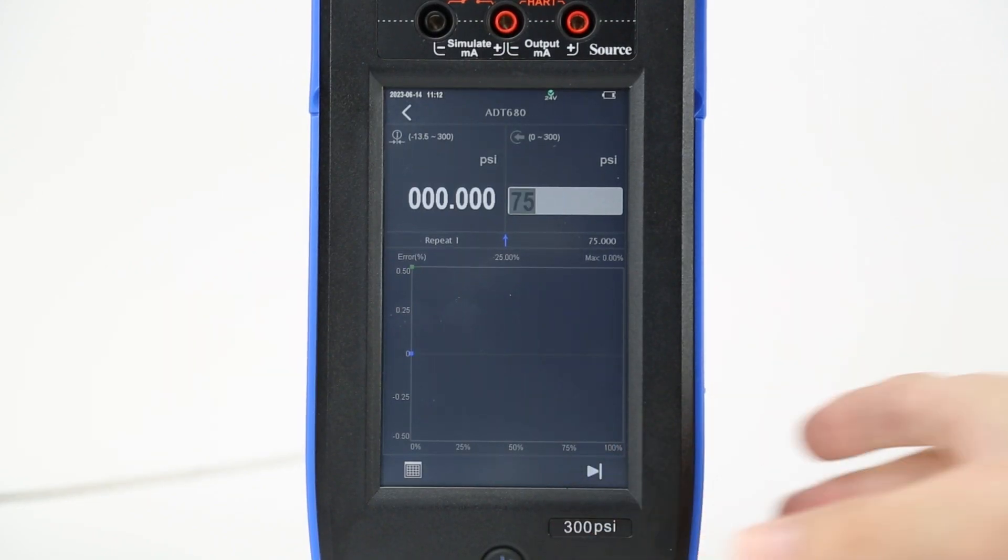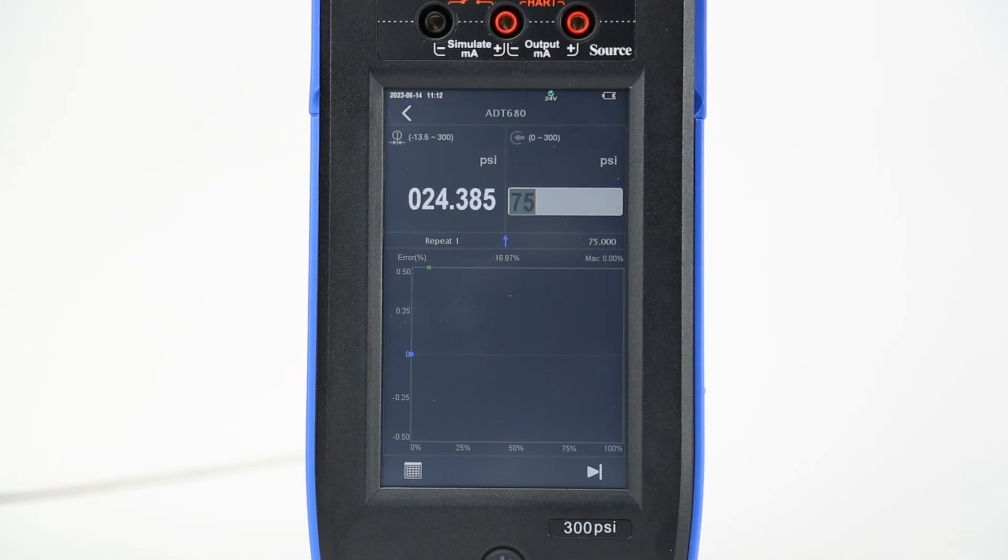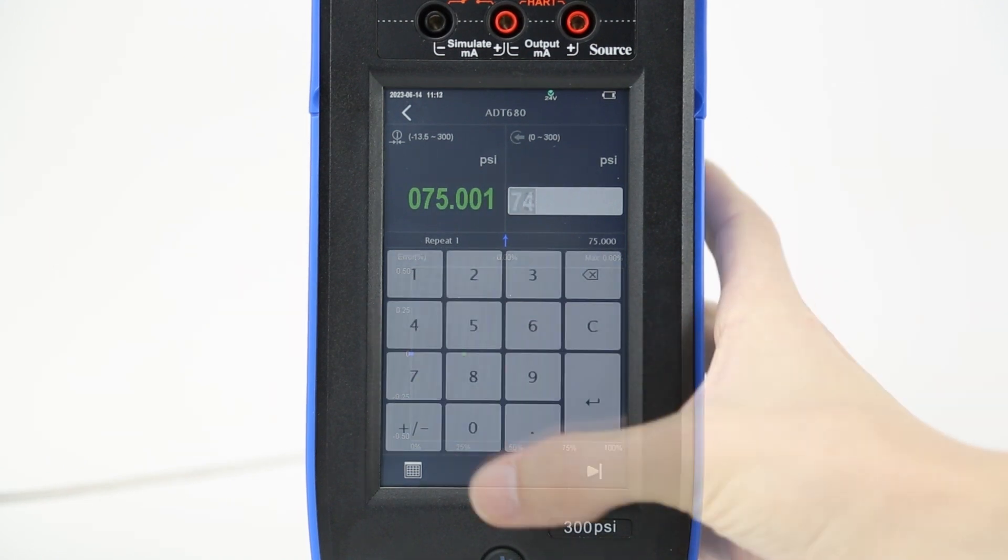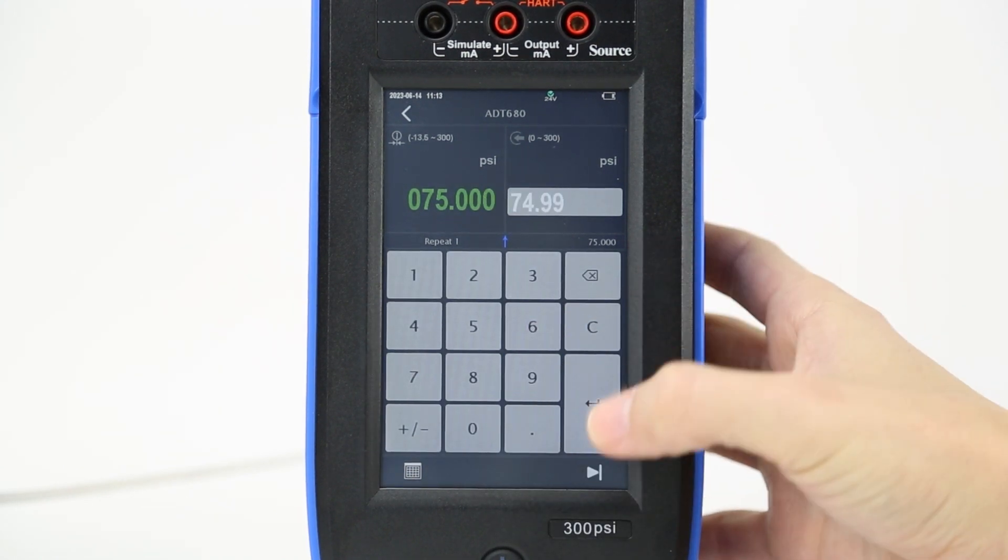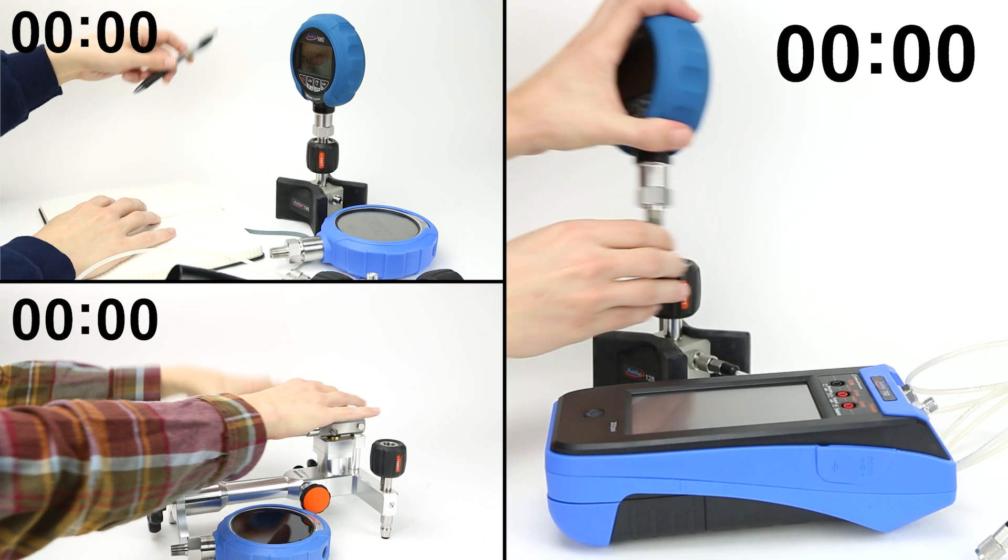Technician 3 will simply press the play button on their 760, and watch it automatically generate pressure to the first set point using its internal pump. Once the reading turns green and beeps to indicate stable pressure, they can enter the value shown on the gauge under test. Each pressure recording will continue in the same manner.